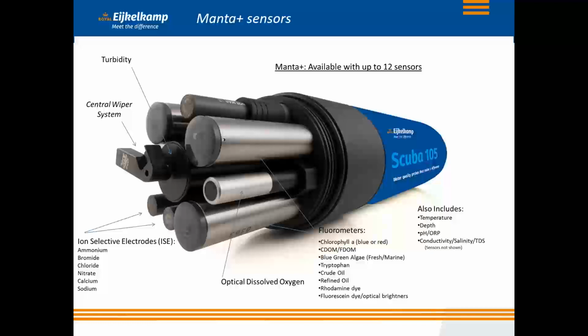As you see, there are ion selective electrodes, optical DO sensors, fluorometers, turbidity, and a central wiper system. The central wiper system is connected to the wiper of the turbidity sensor, which is a rubber one, while the central wiper system has a hairy wiper.